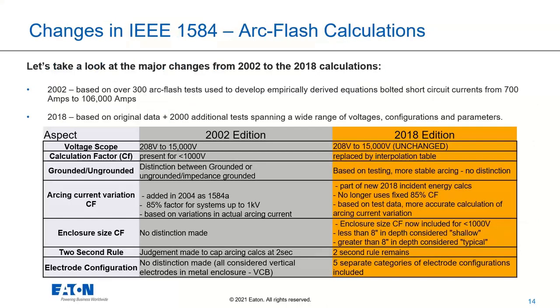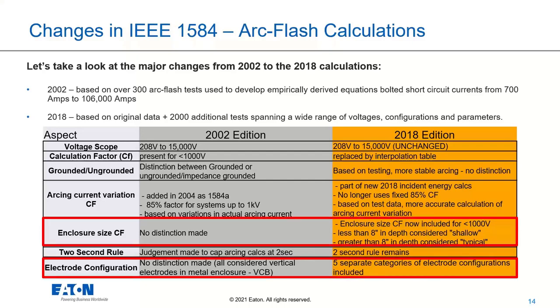The other piece I wanted to highlight in terms of codes and standards would be IEEE 1584 for the arc flash hazard calculations. Many of you might be familiar with this standard, especially if you've used EasyPower or done arc flash studies. Recently, in about 2018, I believe around November, IEEE released an updated version of this standard. The previous version, 2002, technically 2011, which was some semantic updates, but really the 2002 standard or guide was only based on about 300 different arc flash tests, and it was really centered around, I'll call it, one electrode configuration and one enclosure size. Those are the two I really want to highlight here as the biggest differences.